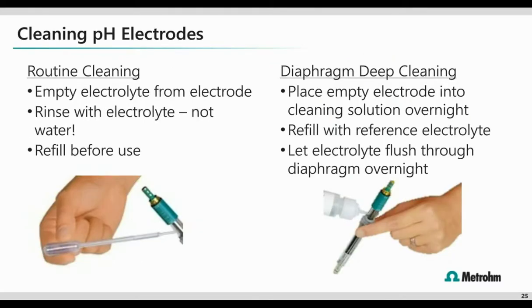If you need to clean the electrode, I've got a couple of buckets here for us. Routine cleaning really consists of periodically emptying the electrolyte from the electrode. Just use a plastic dropper and suck the electrolyte out of that fill port. Go ahead and rinse the chamber with fresh electrolyte. Never fill this body with water. You don't want to put water in there. I know logic tells us, oh, it's salty in there, and water will just dissolve those crystals and rip them right out, but this is actually a really horrible practice for the reference sac that's in there. So even if it takes a couple of passes, fill it and empty it, and then fill it and empty it again. In the end, always refill and store the electrode with electrolyte.